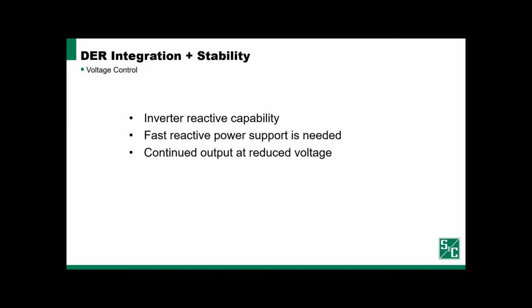As inverter-based resources become a more significant part of our power system and our bulk supply, it's important that they ride through events and continue to support the system throughout the challenges that the system may face. This includes reduced voltage during system faults. It's more important than ever that DERs ride through and continue to support the system as the voltage is depressed to maintain system stability and ensure we can recover.